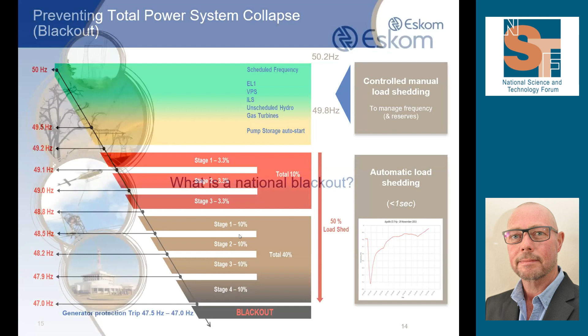All right, so I think first up, we need to understand that it's not just a lack of generation capacity that causes national blackouts. In fact, system operators around the world do similar things to what we do. They have contingency plans, they dispatch generation, they have under-frequency load shedding, and all the precautions that we take. In general, what we find is that large blackouts actually start on the transmission system, where you have a fault on the transmission system. Usually that would disconnect a generator, and then from there we would get some sort of cascading events.